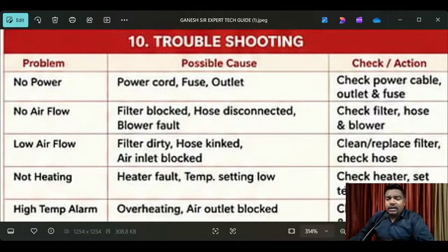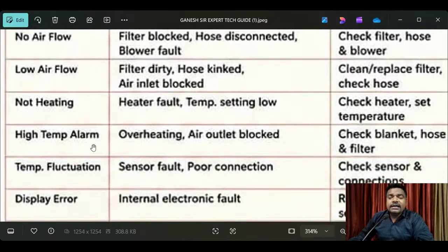Now come here. So what problem will be there? Check heater set and temperature. Okay. Next, high temperature alarm. When this troubleshooting problem comes, see here, what causes will be there? Patient warmer overheating, or air outlet blocked. Okay, blocked. Or what will you do? What action is needed? Check blanket, hose and filter.